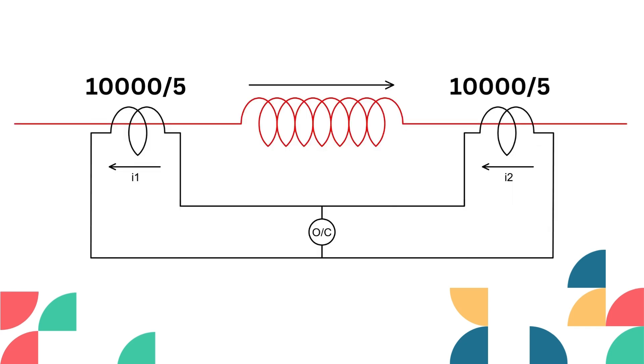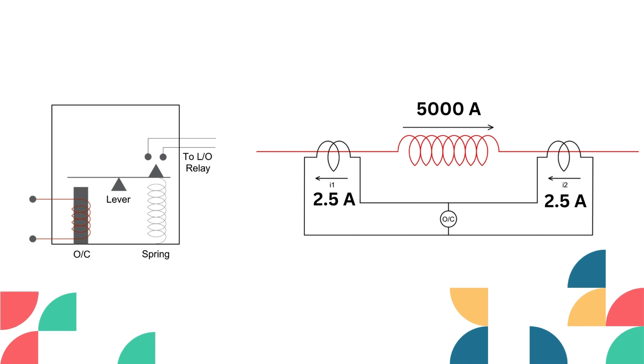Now let's understand how the electromechanical differential relay works. For a 200-megawatt generator, the CT ratio will be 10,000/5 ampere. Let us consider 5,000 ampere current flowing through the stator winding to the load. For that reason, 2.5 ampere current will flow through the secondary winding of each CT. In that case, the differential current will be 0 ampere, which is less than the set value of 0.5 ampere. This 0 ampere will not be able to activate the electromagnet and attract the plunger. The spring is designed such that only when 0.5 amperes flows through the electromagnet will it attract the plunger and make the trip contact.